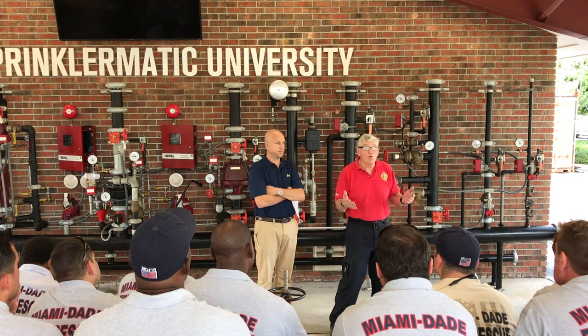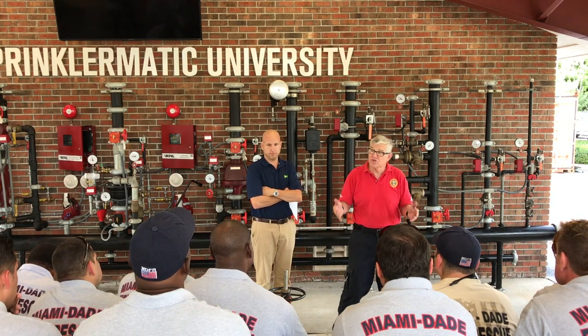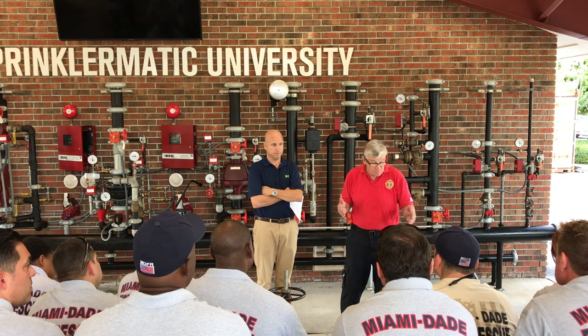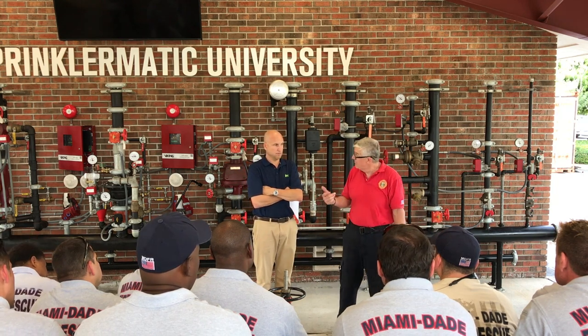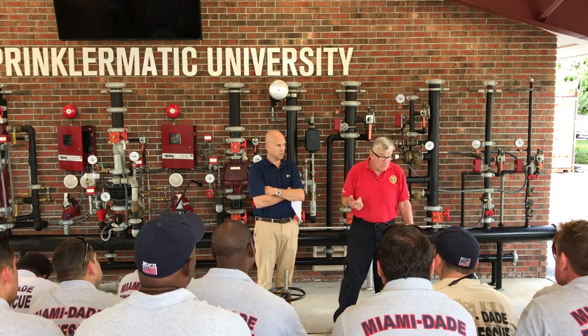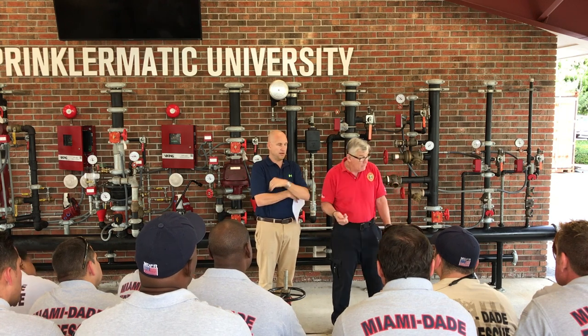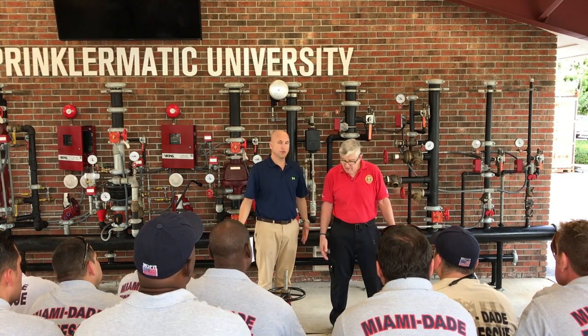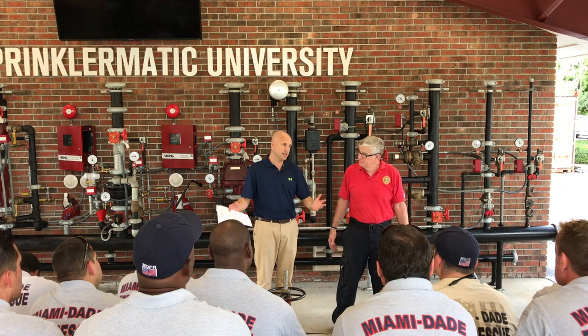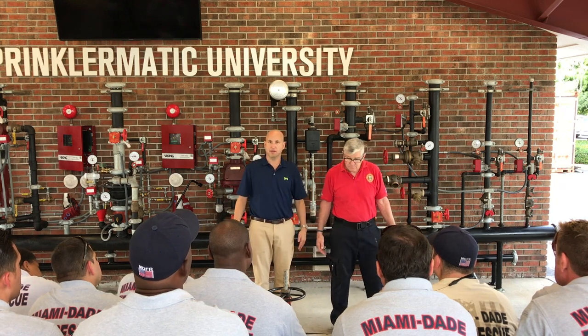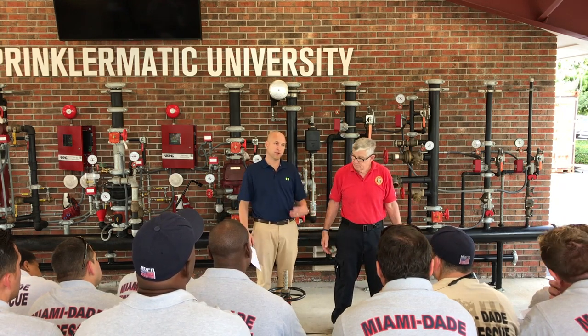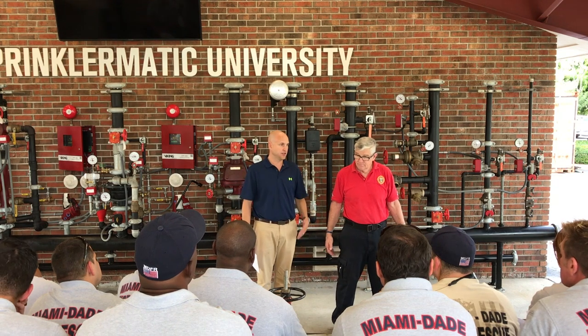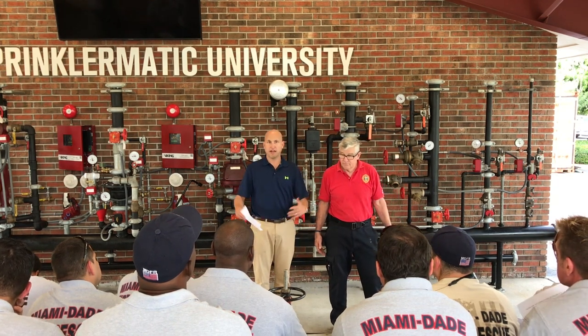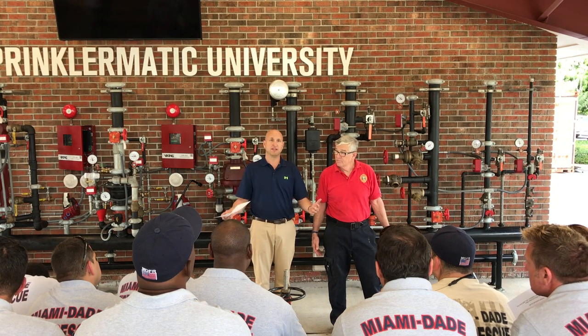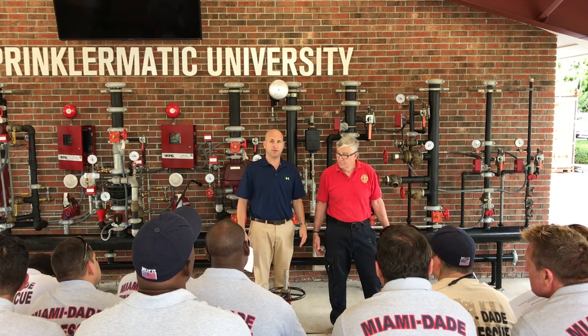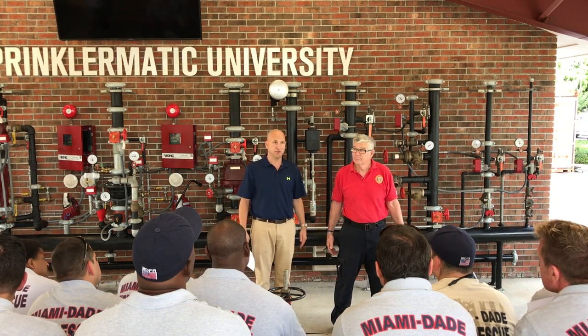So we've got to get the word out to our authority having jurisdiction that the PRVs need to be flow tested every 5 years for a hose outlet, pressure tested once a year. And exercise fully, yes, once a year. So this is basic exercise stuff, guys. We know it's not happening. We know for sure it's not. And this is one of those deals where education is key. And I think when you guys start to understand a little bit more about these, and you go out to the world and we get this message going, it's going to be good for everybody. This is literally the last line of defense once you guys get there.